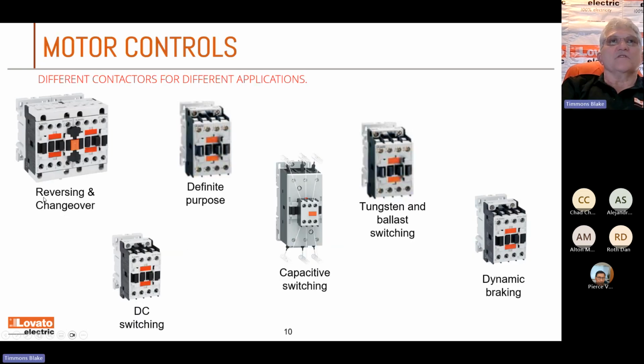Different contactors for different applications. As I mentioned earlier, we have our reversing and changeover contactors. It's a double thing with a mechanical interlock in between. We have definite purpose contactors. This is the one that gets people a lot. A definite purpose contactor is a contactor that's certified for definite purpose. What is definite purpose? What do you mean? Well, most of our contactors are going to be sized for 2 million cycles. The industrial world, we need a lot of cycles.